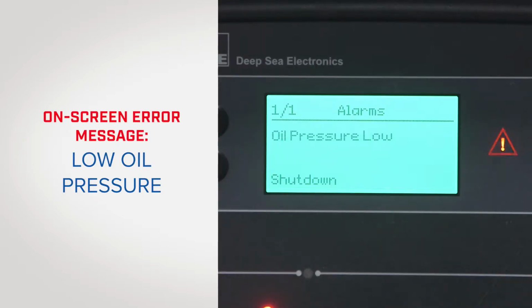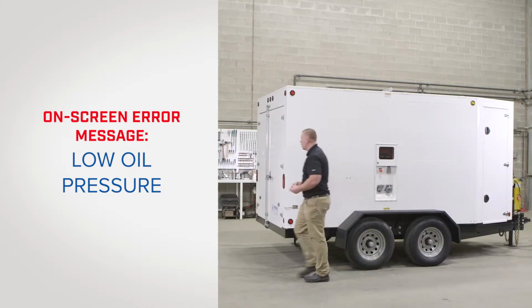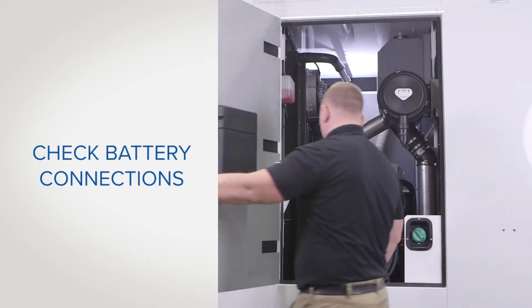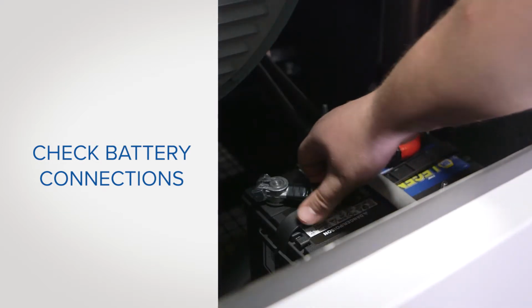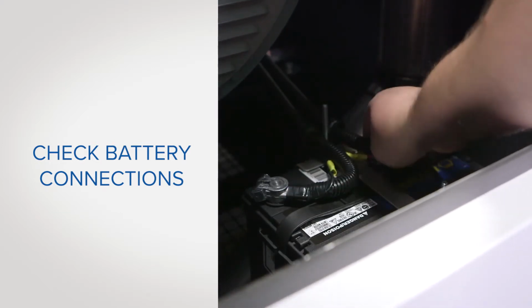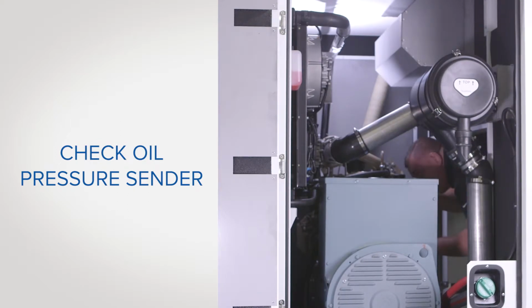You may see a low oil pressure warning on the control panel screen. A low oil pressure warning can occur if the oil pressure sender is damaged. First, check your battery connections. If tightening the battery connections does not resolve the problem, test to see if the oil pressure sender is working properly by checking the ohms. At 0 psi, it should read 240 ohms. If the reading is not 240 ohms, you will need to replace the oil pressure sender.